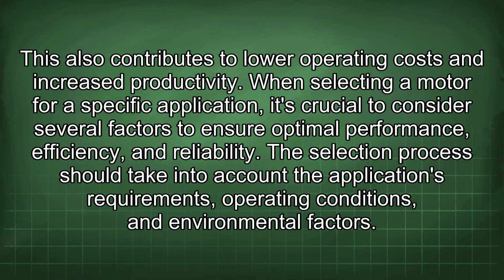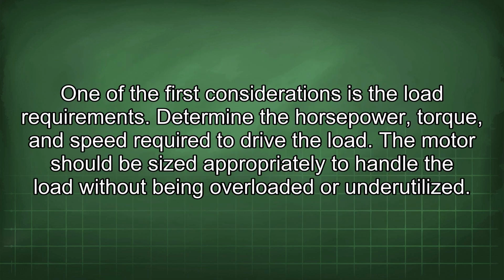When selecting a motor for a specific application, it's crucial to consider several factors to ensure optimal performance, efficiency, and reliability. The selection process should take into account the application's requirements, operating conditions, and environmental factors. One of the first considerations is the load requirements. Determine the horsepower, torque, and speed required to drive the load. The motor should be sized appropriately to handle the load without being overloaded or underutilized.